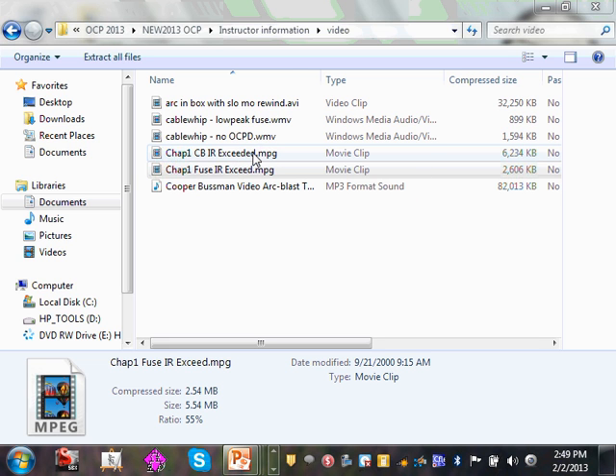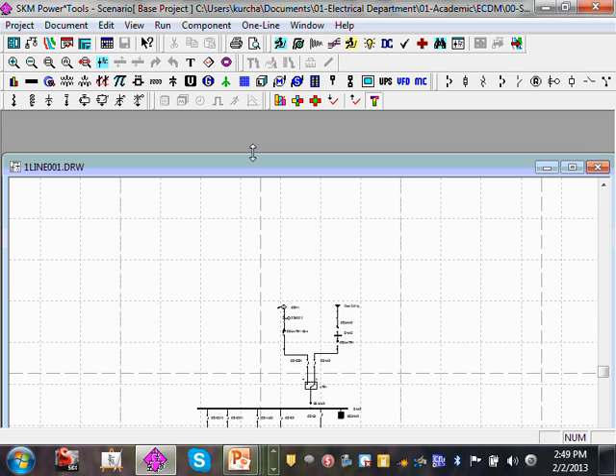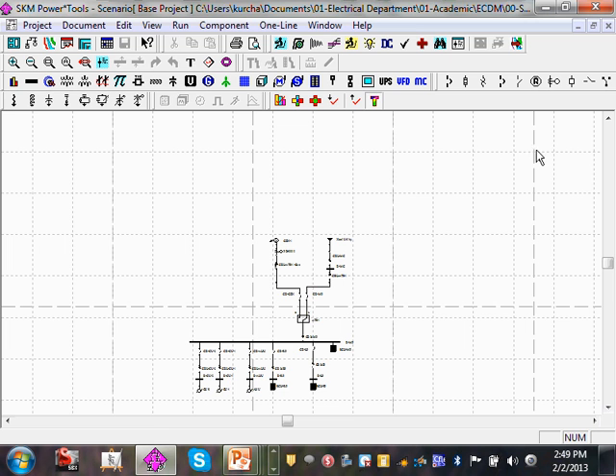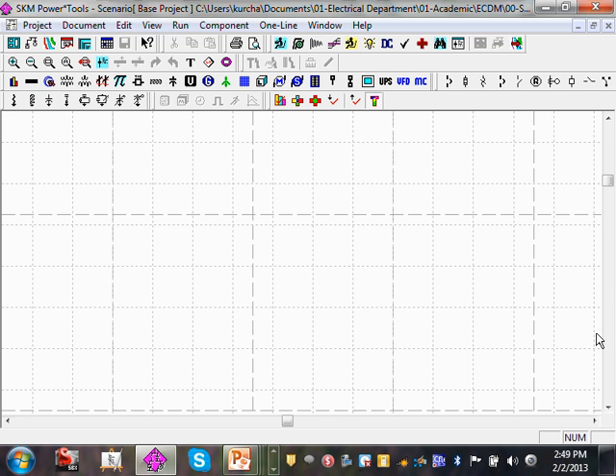If I told you, I have a continuous machine, size me a circuit breaker, Chad, and it's 100 amp. No problem. The code says continuous machines, guys, have to be sized based on 1.25. Take the 100 amp, multiply it by 1.25, that gives me 125 amp, and I stick a 125 amp circuit breaker right ahead of it, right? And I size the cable to match the 100 amp. Done. That's the normal operating condition for the circuit breakers. Under normal operating condition, the circuit breaker has to handle 125 amp. Under abnormal conditions, your circuit breaker has to handle the short circuit and the ground fault.